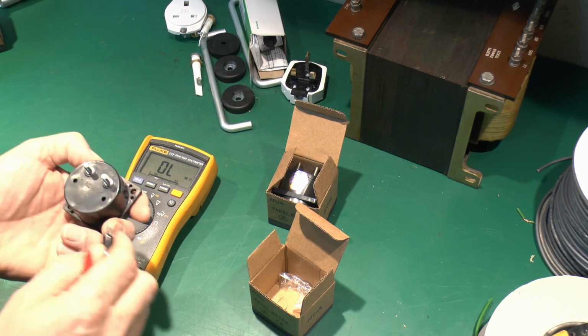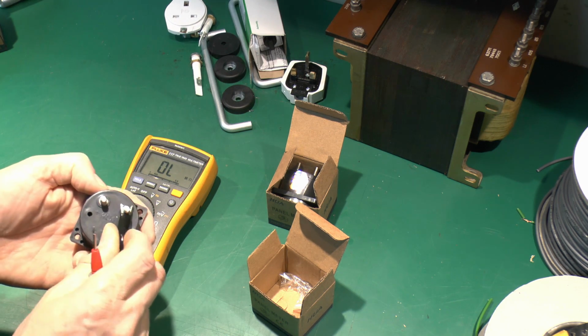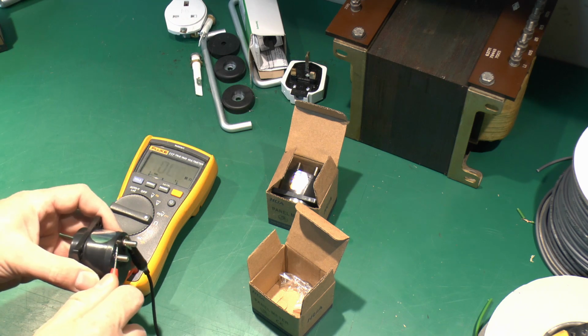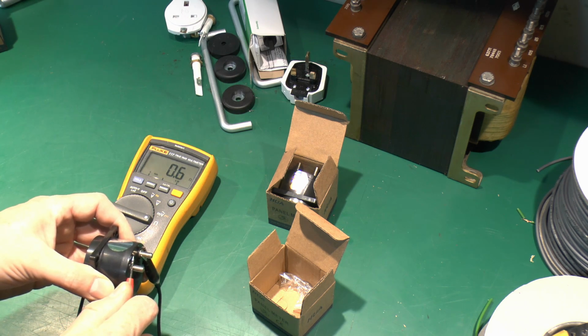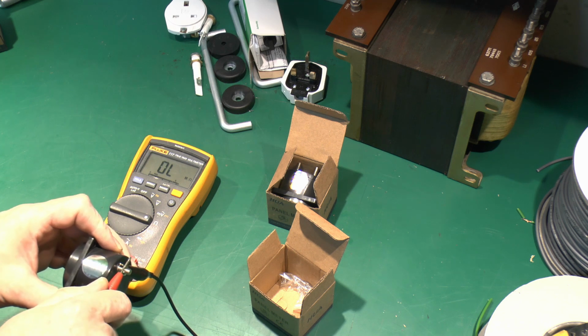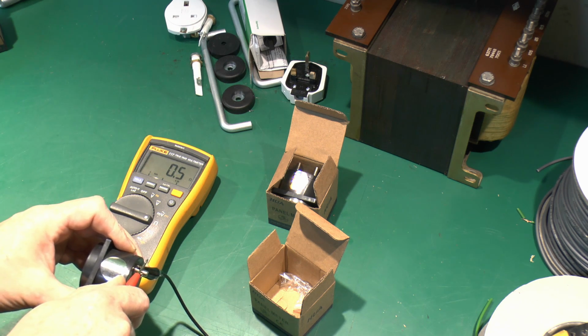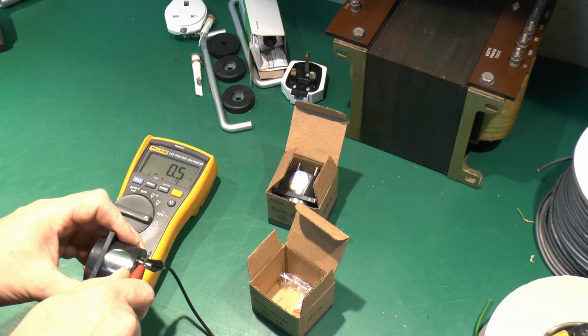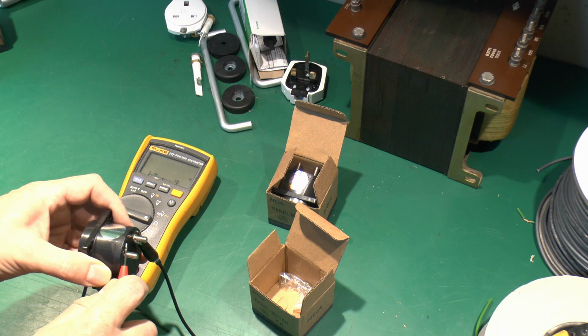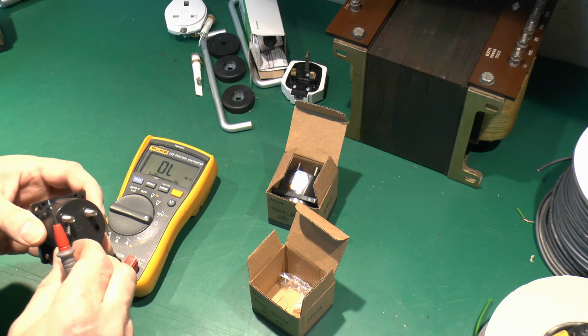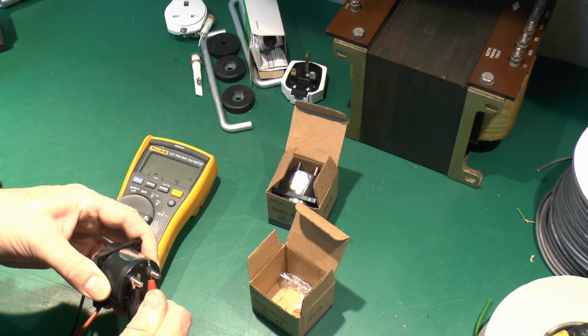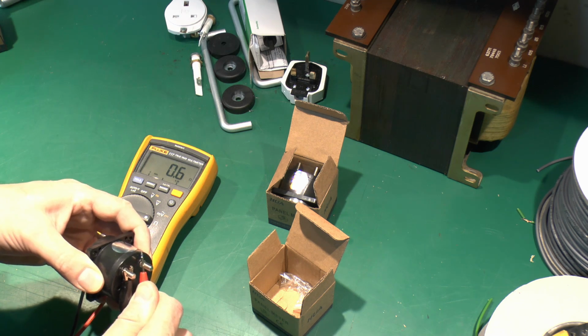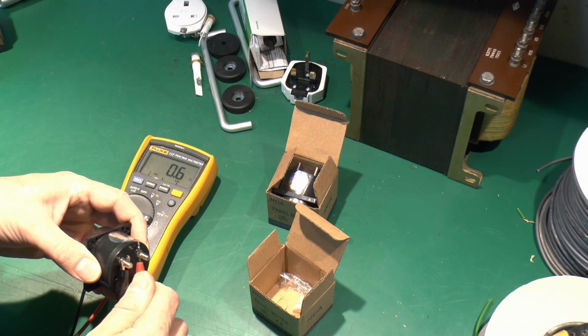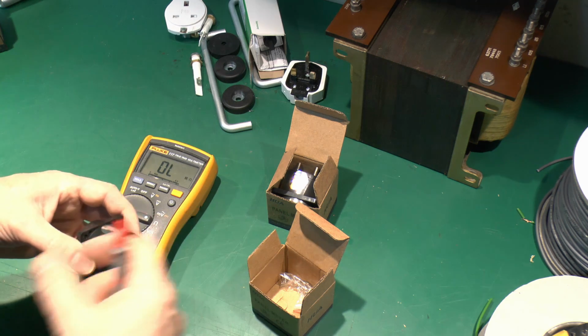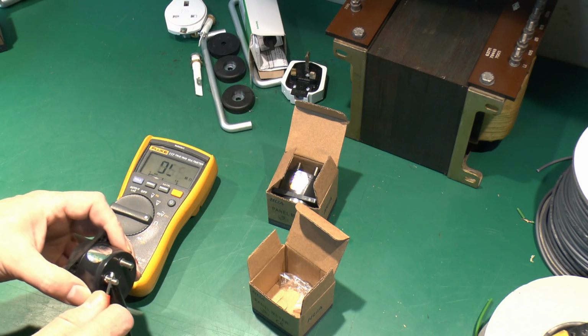Now again, these are marked plus and minus, but let's try the proper way round, and we should get extremely low resistance - so 0.6 ohms. Let's check what the leads measure: 0.6 ohms, 0.5, so we're looking in the region of 0.1 ohms. Again, that's perfectly reasonable - basically we want it to be as close to 0 as possible. Oh, it's the same in the other direction, which is exactly what you'd expect, because current flows in both directions on AC.